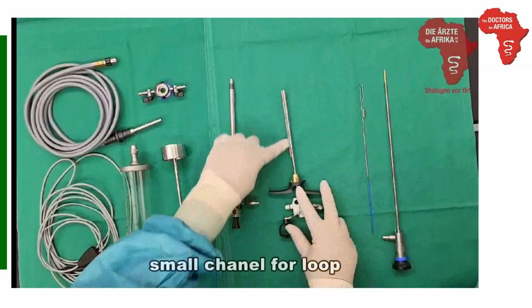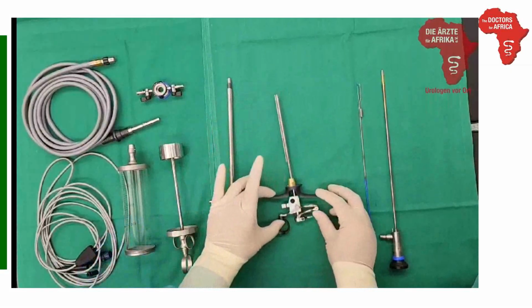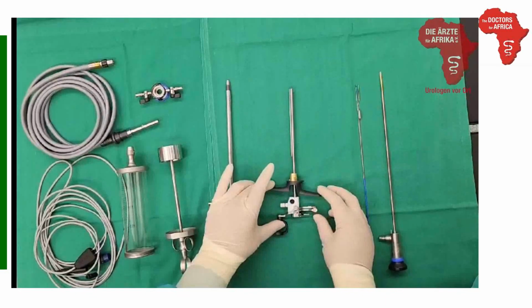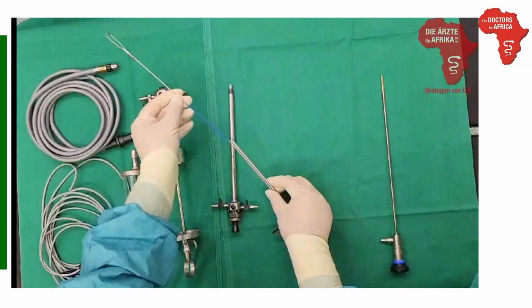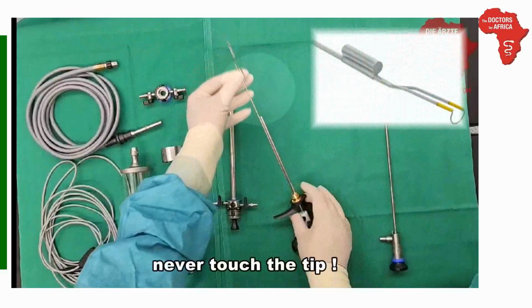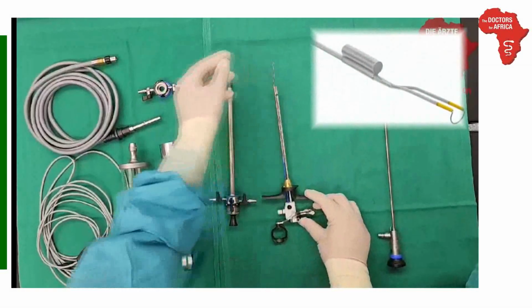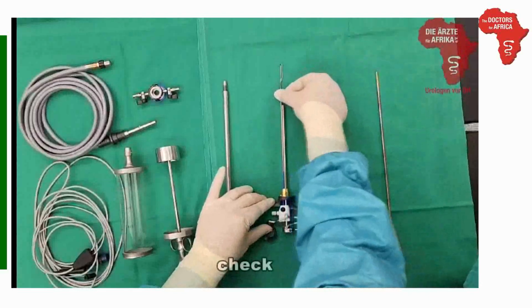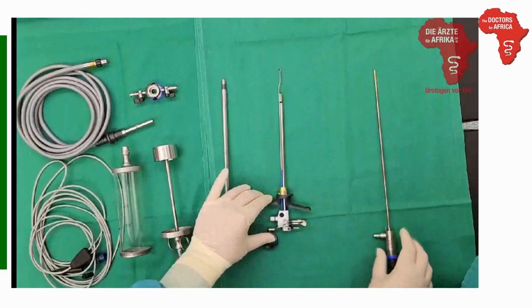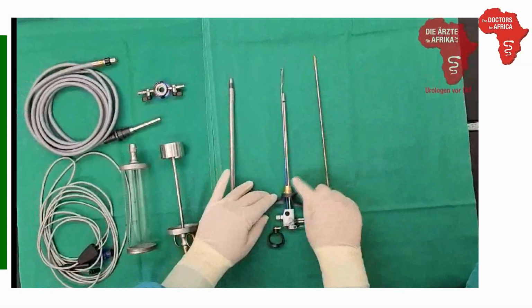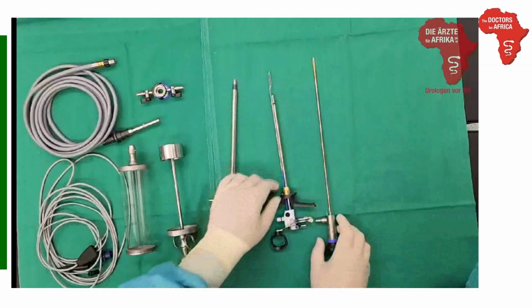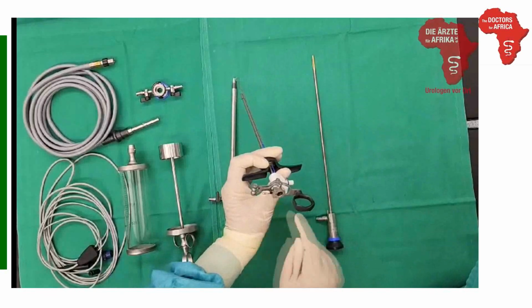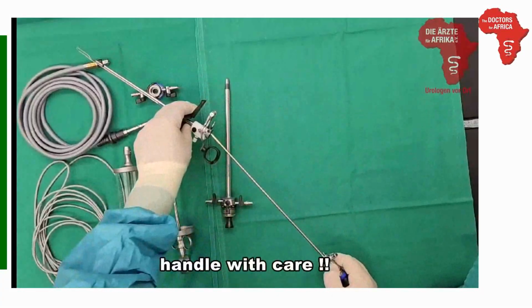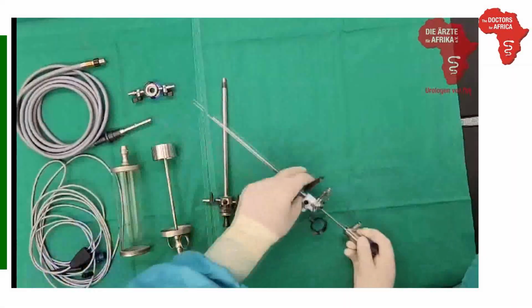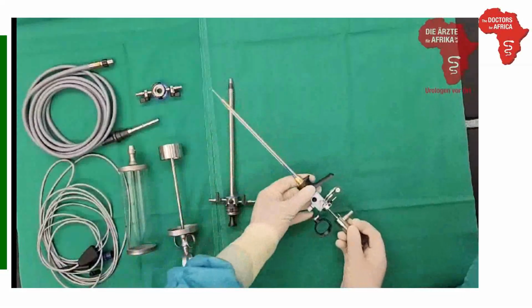This is the working element with a small channel that is used to introduce the loop. And by moving it in this way, you move the electrode. Introduction of the loop into the lesser tube. You also hear a click. Always check if it's firmly attached. Then we have the telescope that goes into the larger tube in the working element. There's a small opening. Introduction must be done very carefully. Don't bend the telescope. It's very vulnerable. You also hear a click.